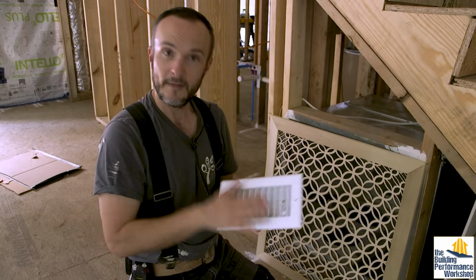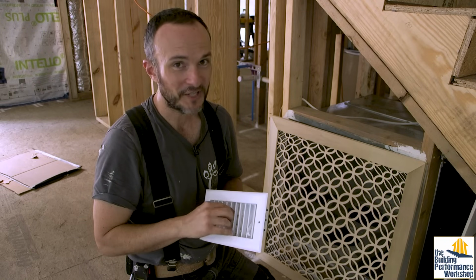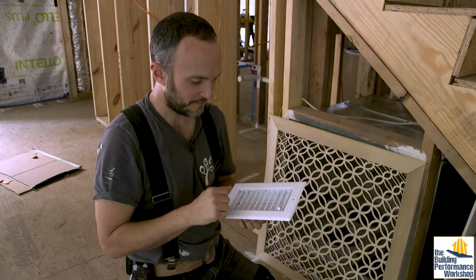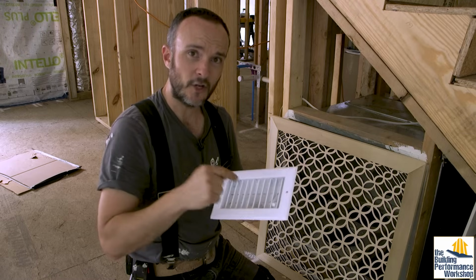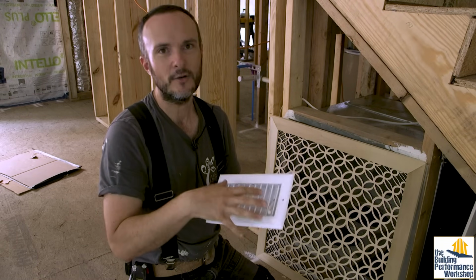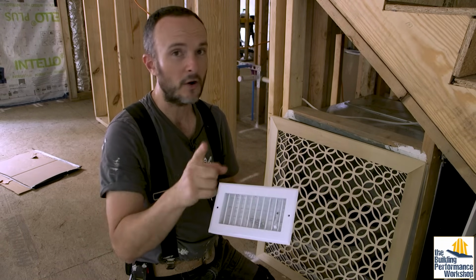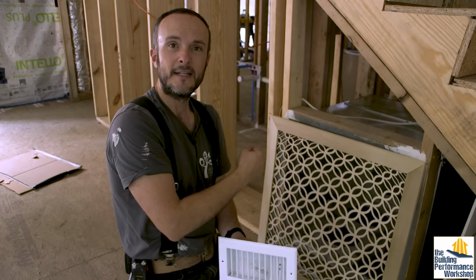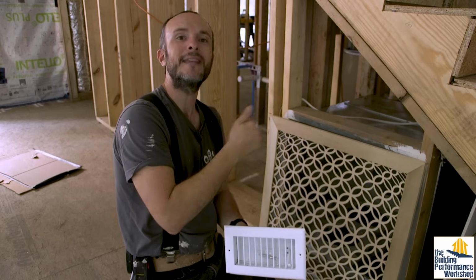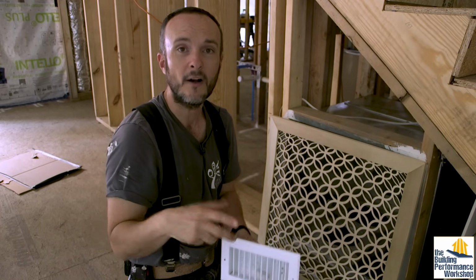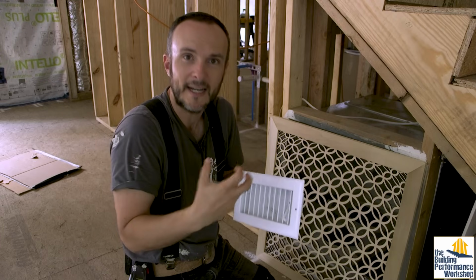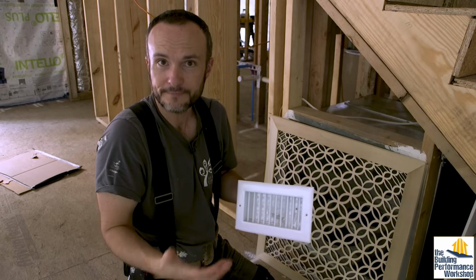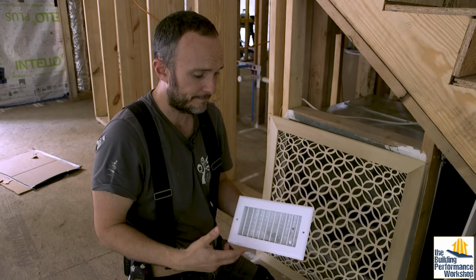Crazy. Number one, that's a sign that there was not a duct design done on that house. That's a clue. Secondly, this is going to do two things. It's going to slow down or prohibit airflow out through this, but also it's going to introduce back pressure upstream. So it's going to make everything up to the air handler potentially also work harder because it's going to start squeezing and basically increasing your blood pressure, if you think of your house as a body again.